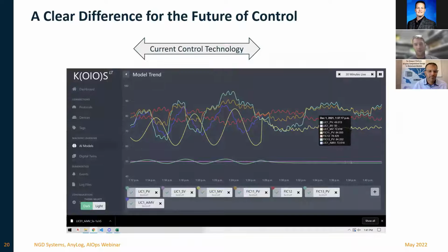What you're going to see here is the difference from normal PID control. Just here on the left-hand side of the graph, you can see this is normal PID. This is optimal control for most systems. If an engineer today was to look at that, they would say, okay, that's not bad, right? The green line down there at the bottom is somewhat staying close to the little magenta line, even though the process is swinging pretty hard.